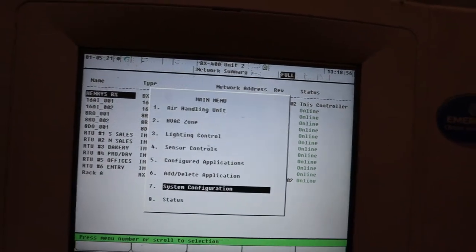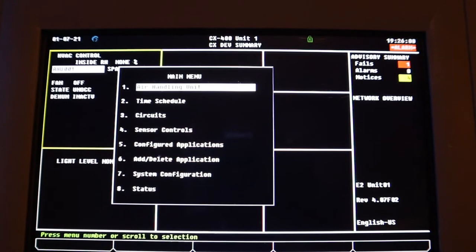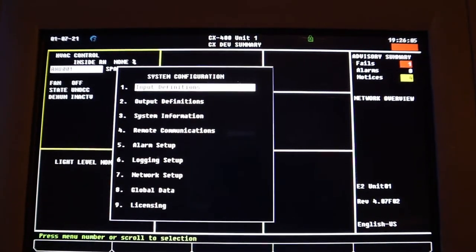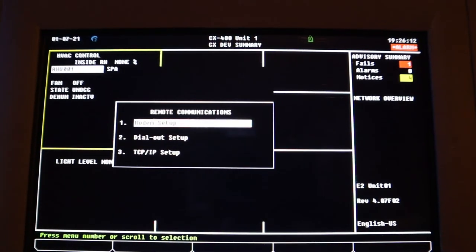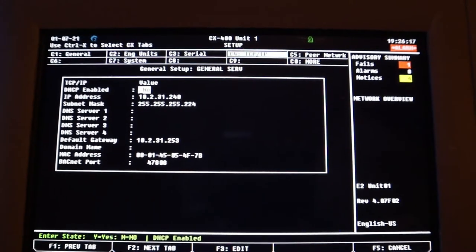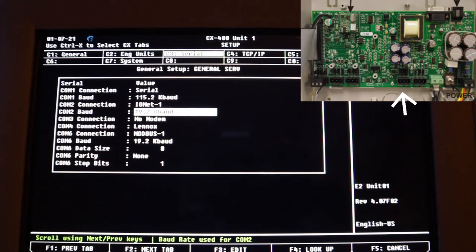I know when you guys run these kind of calls it's not always going to be that easy, so let me show you an extra step. This is a controller I have at home for training. Hit menu number seven, then number four — remote communication, number three IP setup — and back up to C3 serial. Make sure if you have the wires going to COM4, it's set up as Lennox.